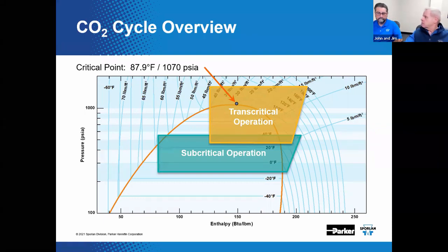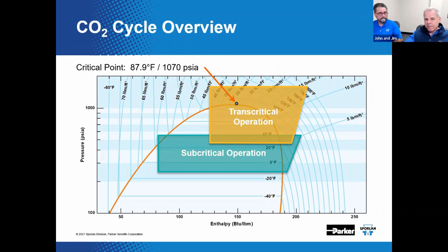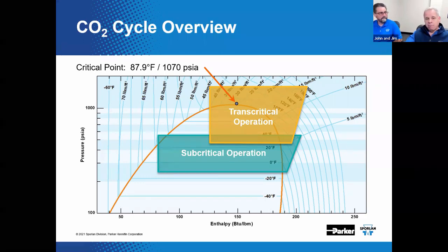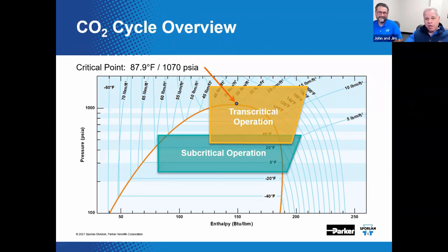Oh gosh, here's a pH diagram for R744, a la CO2. Pulling out the pH diagrams on us again, Jim. What is a pH diagram, John? That would be pressure versus enthalpy, focusing in on the vapor dome or the saturation dome of the refrigerant, which is where we operate our cycles, obviously. So you're telling me it's a graphical representation of physical and thermodynamic properties generated by the equation of state for the refrigerant? You said that, not me. No. In this diagram, we have superimposed both a transcritical refrigeration cycle and a subcritical refrigeration cycle upon the pH diagram. So what does this mean?